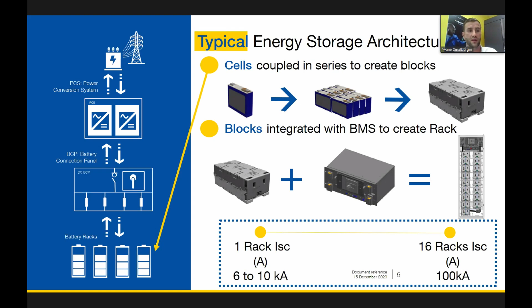But then when we start putting more and more racks together, as an example, 16 racks, we have short circuit ratings of up to 100,000 ampere. This makes it tricky to be able to prevent battery failure modes and catastrophic events like fire. I know most of you could be aware of the early days of storage in Korea, where there were many catastrophic failures. And how do we address this?